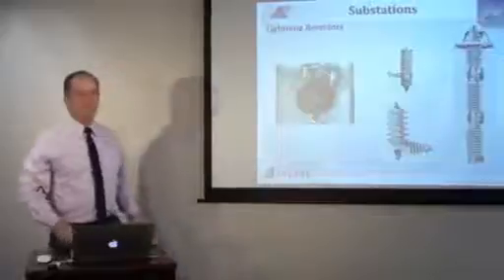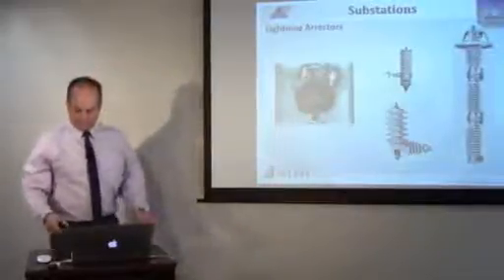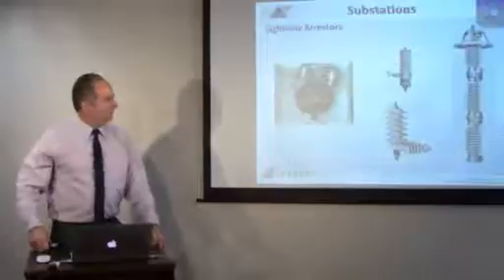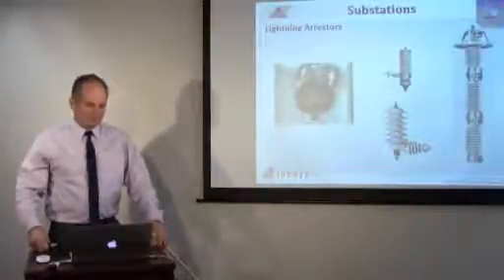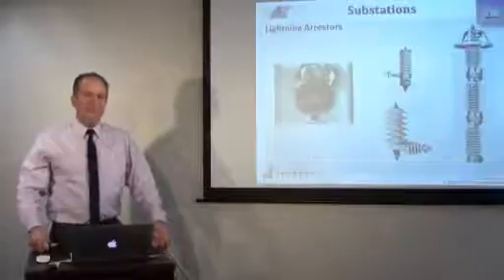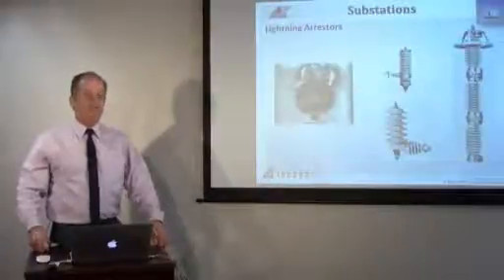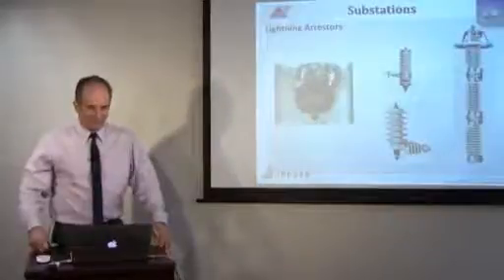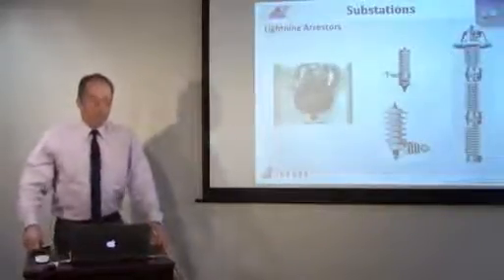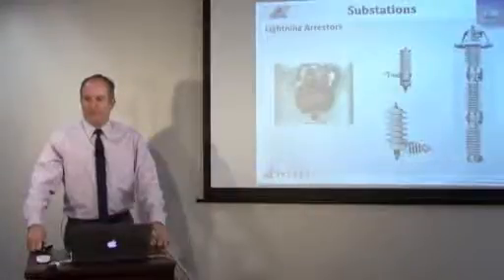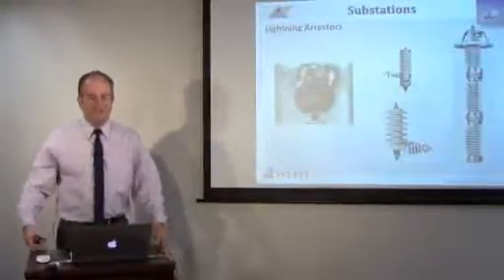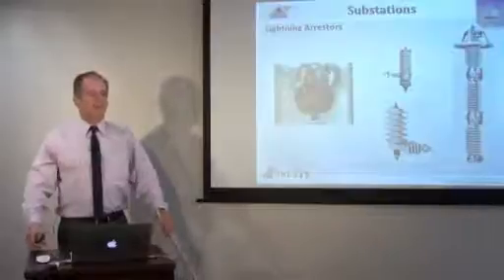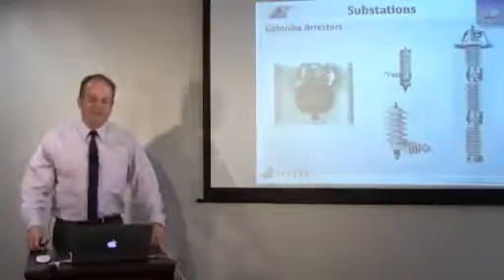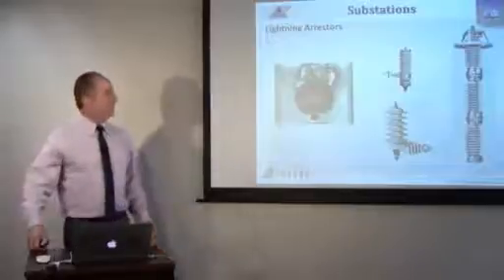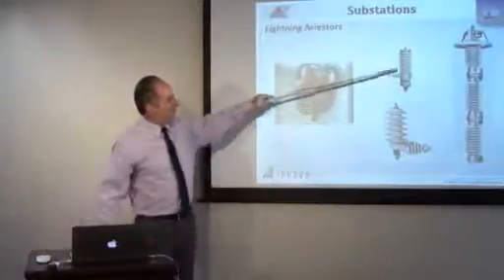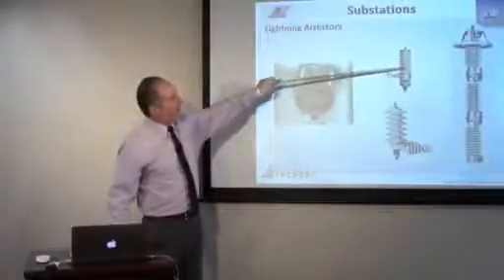Okay, now let's talk a little bit about lightning arresters. The purpose of a lightning arrestor is to be the weakest link in the insulation chain on the system. In other words, we put our wires up and space them so that they can have a certain amount of dielectric strength. And then the first thing that should fail is the lightning arrestor. In the older ones, there were gaps. There was an air gap in there.